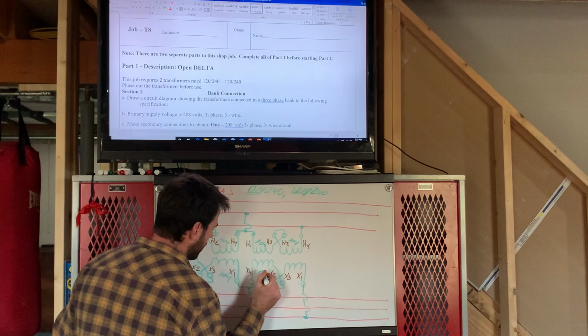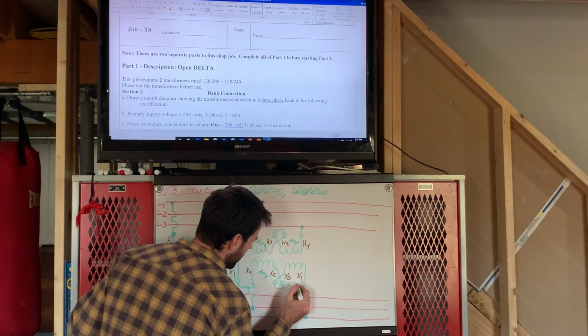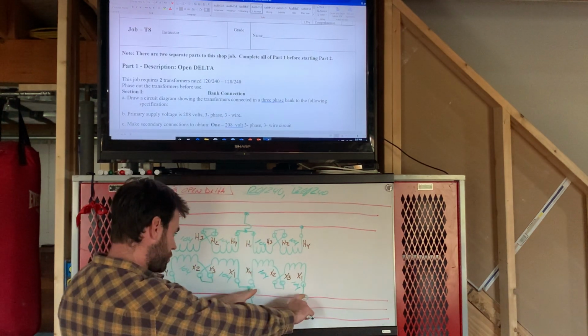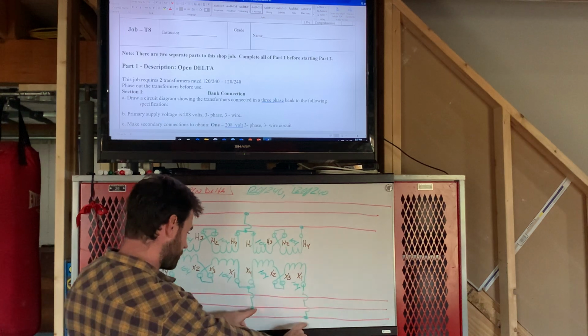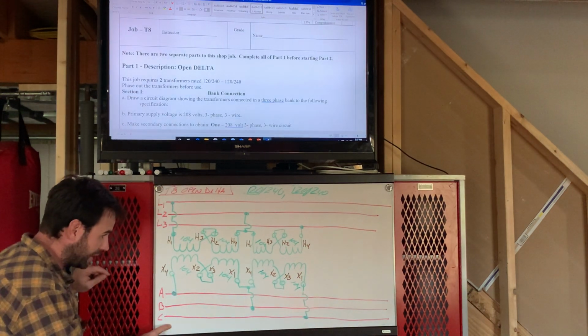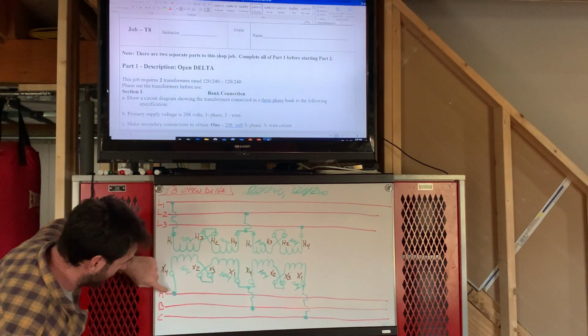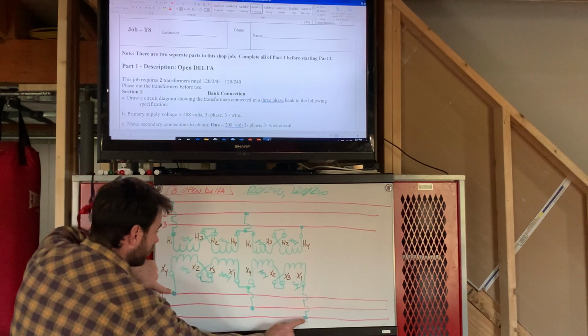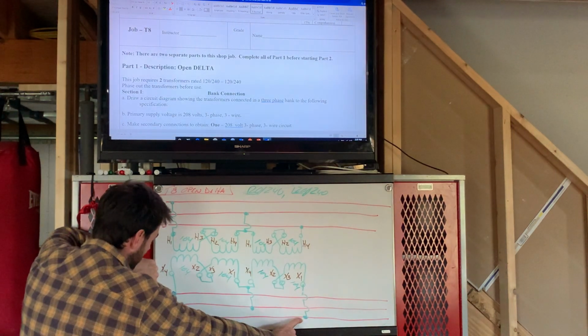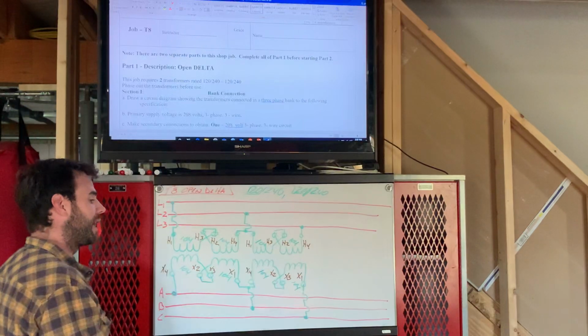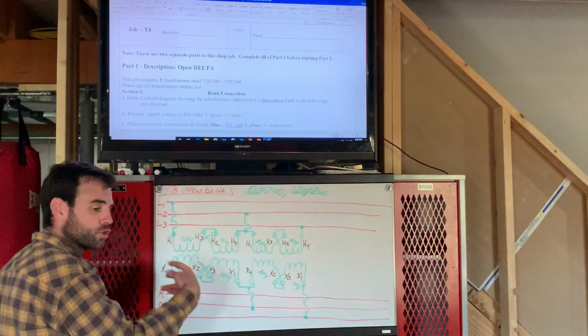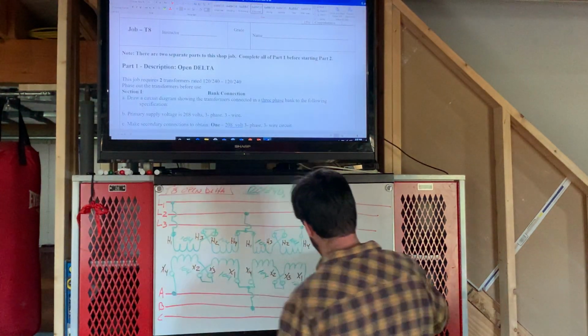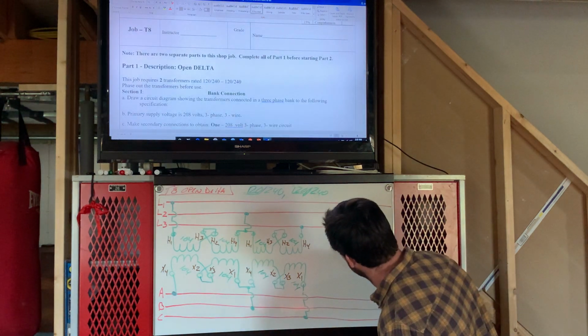Well, I've got 104 on this coil, 104 here. I'm going to measure 208 between these 2 points. So 208 between B and C. Then if I measure between A and C, I'm also going to measure 208 volts. They consider this an open delta because it's open on the one side. I'm just going to draw the secondary side here. So if we draw transformer 1, we have a coil.